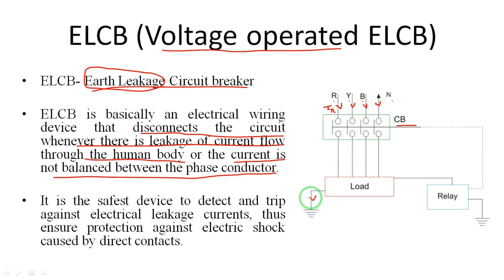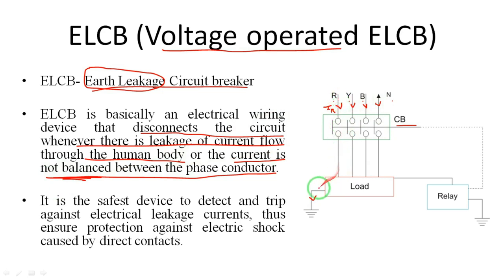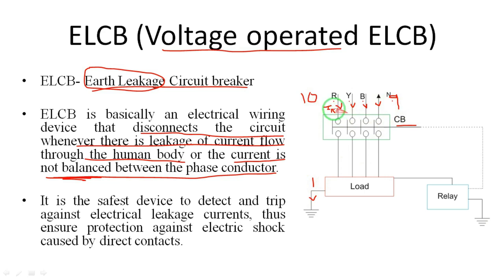If any earth leakage current occurs, then the incoming current is not equal to the outgoing current — that is an imbalance. For example, if the incoming current is 10 amperes and the leakage current is 1 ampere, then the return current will be only 9 amperes. Because of this leakage, that leakage current passes through the relay to the ground via the parallel connection.